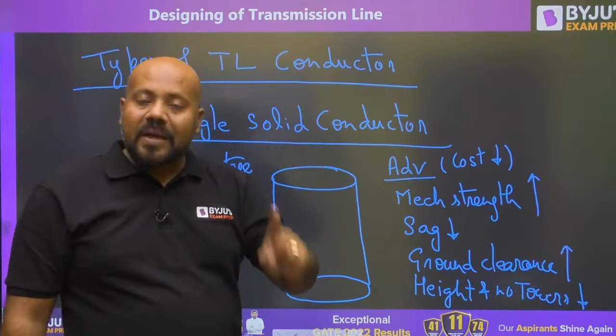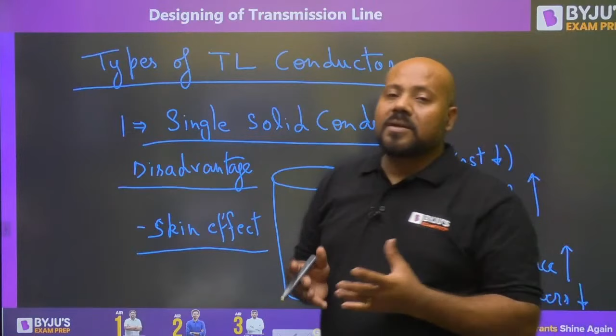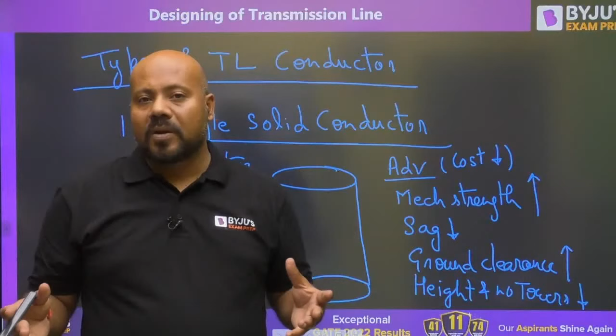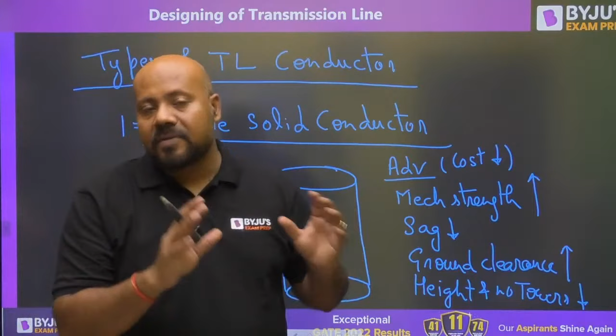There is one big disadvantage, that is skin effect is going to be very high. Because of skin effect, the AC resistance of the conductor is going to be higher than the DC resistance. More resistance means more ohmic losses. More ohmic losses means less efficiency. This is the case.